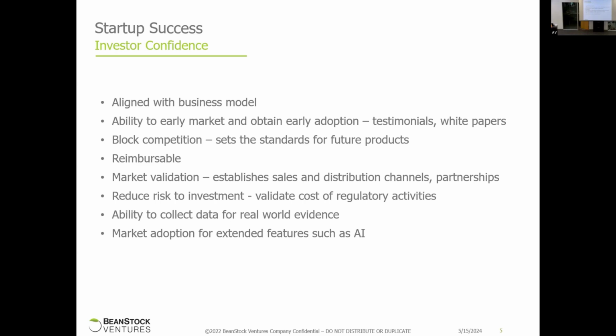So if I get a question at the end, what does a regulatory submission generally cost? It's going to depend. It's really going to depend on your product. If it's a PMA, it could be in the millions. If it's a 510K, it could be 250, 500K, somewhere around there. And when you're doing a 510K, it's going to depend on how much work you can do internally versus outsourcing. The ability to collect data for real world evidence.